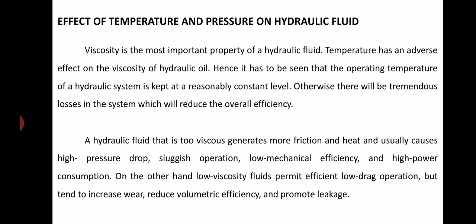Effect of temperature and pressure on hydraulic fluid. Viscosity is the most important property of a hydraulic fluid. Temperature has an adverse effect on the viscosity of hydraulic oil. Hence, it has to be seen that the operating temperature of a hydraulic system is kept at a reasonably constant level; otherwise, there will be tremendous losses in the system which will reduce the overall efficiency.